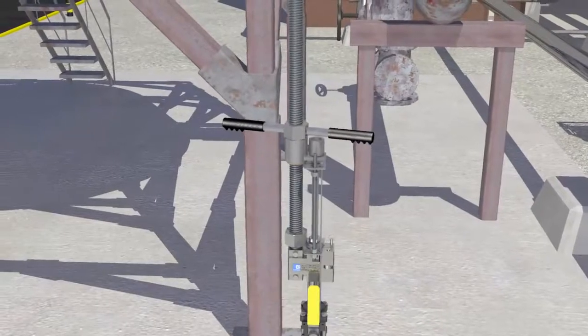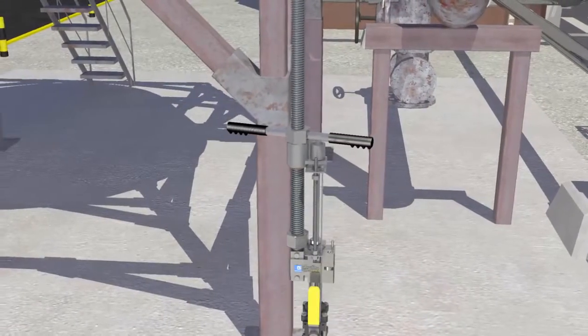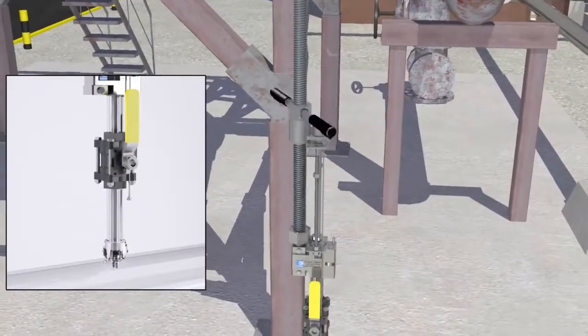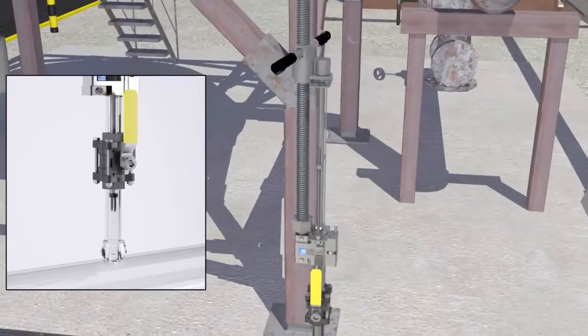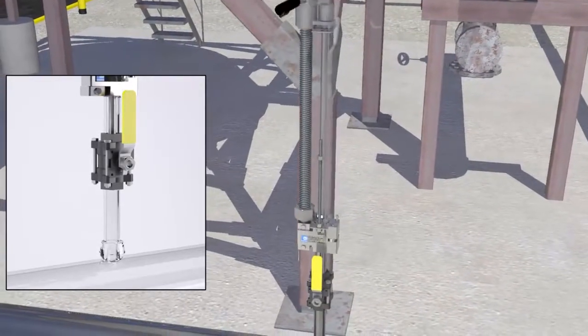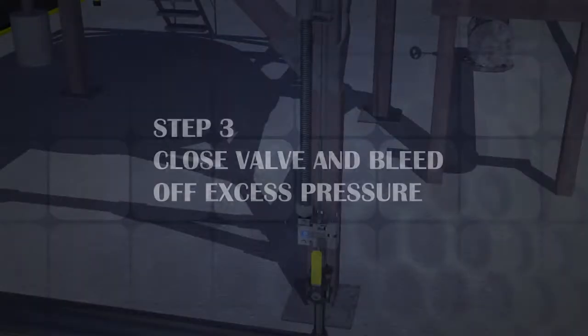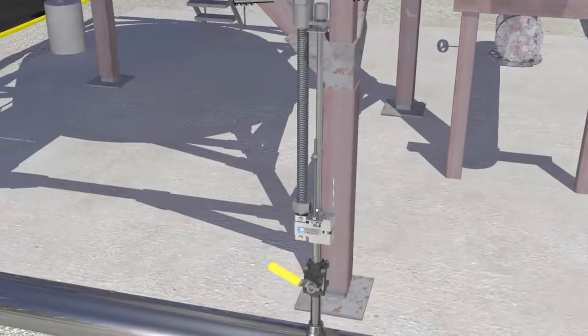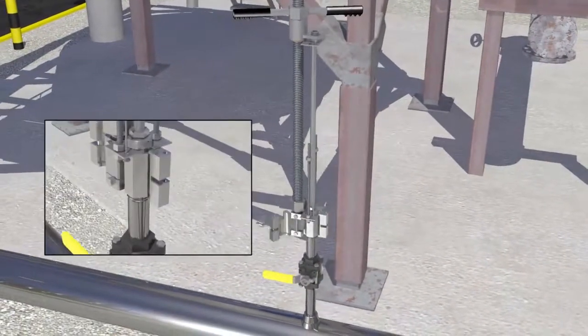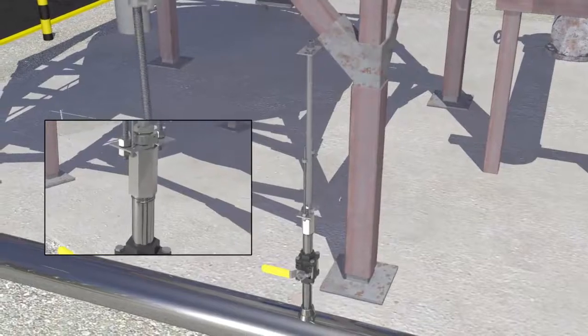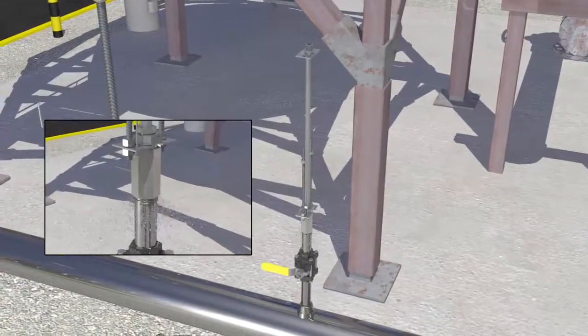Remove the probe by rotating the handle nut counterclockwise, allowing system pressure to drive the probe out until it's fully retracted. The safety cable will become fully taut, which will allow closing of the access valve assembly. Step 3. Close valve and bleed off excess pressure. Close the access valve and remove the retractor tool from the probe. Slowly loosen the stuffing box body to release a small amount of pressure contained inside the stuffing box and nipple.